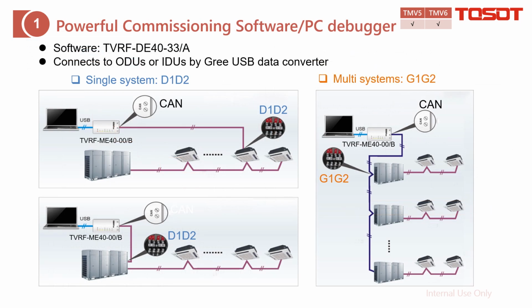As for the wiring, you can just follow these pictures, which are on the startup page of the software. For a single system, use D1, D2, either from the indoor unit or outdoor unit. After that, connect to this converter, then from the converter to the PC. For the multi-system, also on the master outdoor unit, from G1, G2.